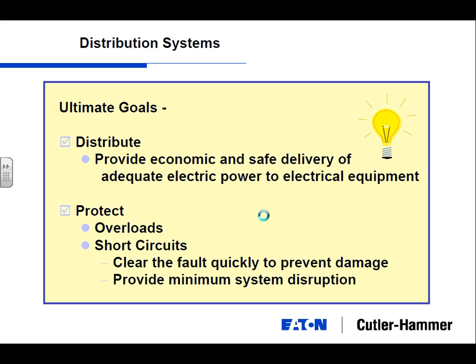Arc flash energy is if I have some type of short circuit, and in reality, you'll see a flash, a bang, a puff of smoke, anywhere from just a little flash, bang, puff of smoke to, did anybody watch that, what was it, the San Francisco Monday Night Football game? The 49ers were playing, and all of a sudden all the lights went out, and they had that camera, and you saw this big blue bang out, that was a block away. That would be a short circuit.